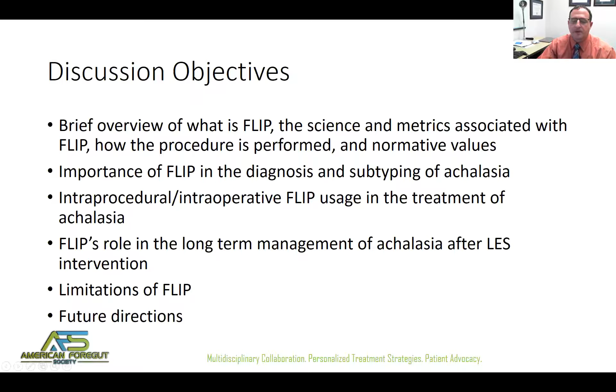So what is the FLIP? Well, simply put, the FLIP is a device that measures luminal cross-sectional area and pressure in the esophagus using impedance planimetry, allowing for the measurement of distensibility. The FLIP hardware includes a catheter with a highly compliant balloon. Within the balloon, there are 16 paired impedance planimetry electrodes and a solid-state pressure transducer located distally. The FLIP catheter is available in two sizes, an 8 centimeter and a 16 centimeter catheter.